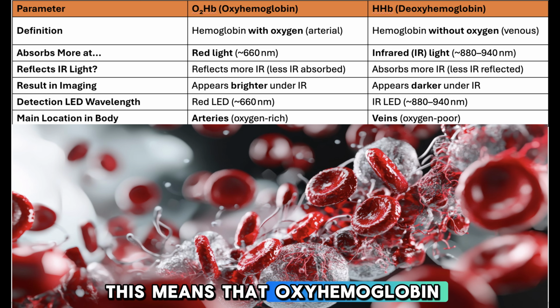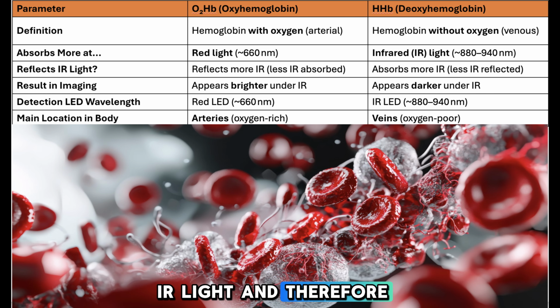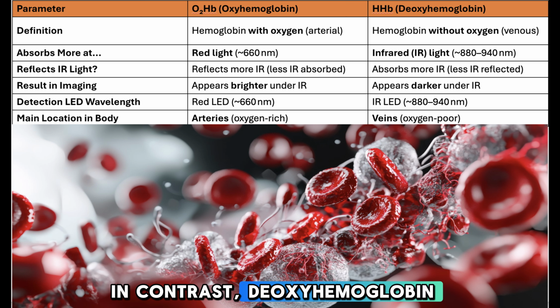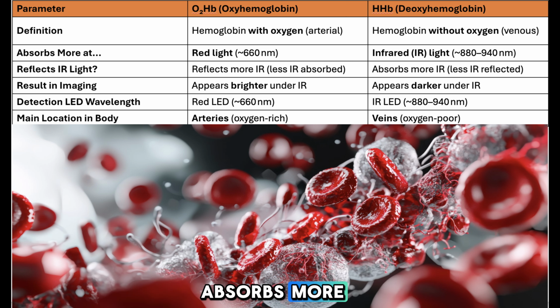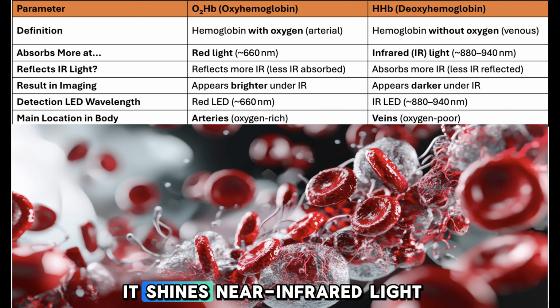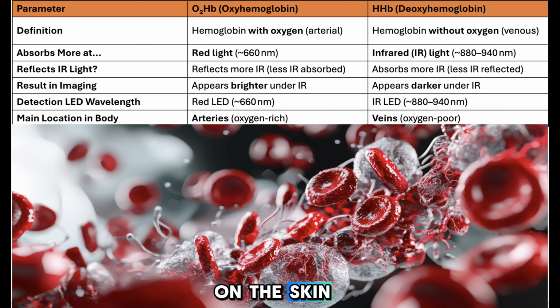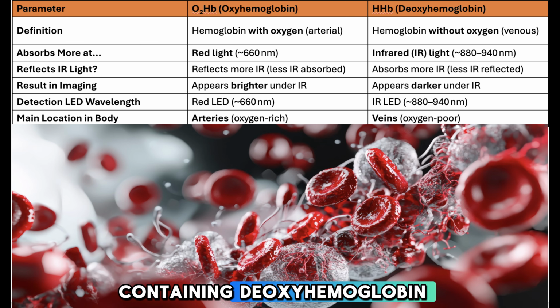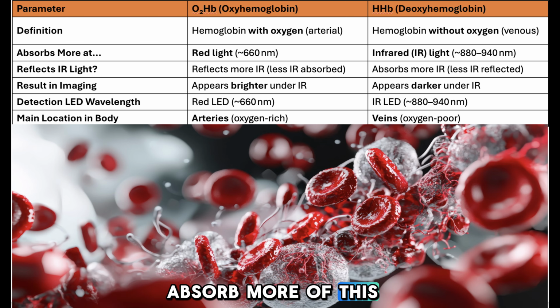This means that oxyhemoglobin reflects more IR light and therefore appears brighter under IR imaging. In contrast, deoxyhemoglobin absorbs more IR and appears darker. AccuVein uses this principle to detect veins. It shines near-infrared light on the skin, and because veins, containing deoxyhemoglobin, absorb more of this light, they appear as dark lines contrasted against the surrounding brighter tissue.